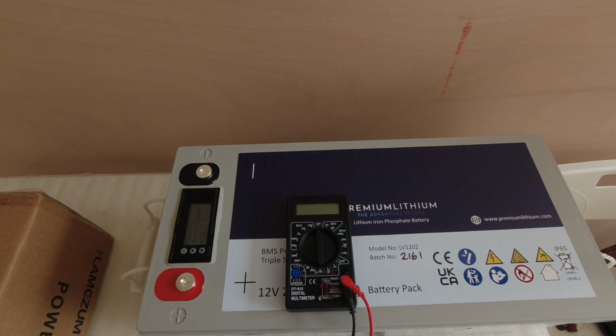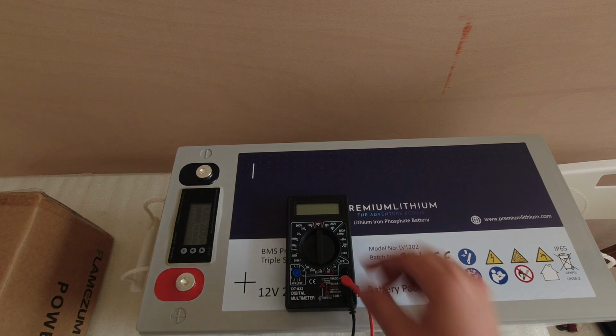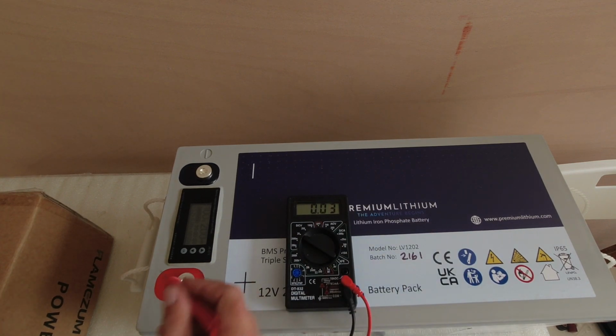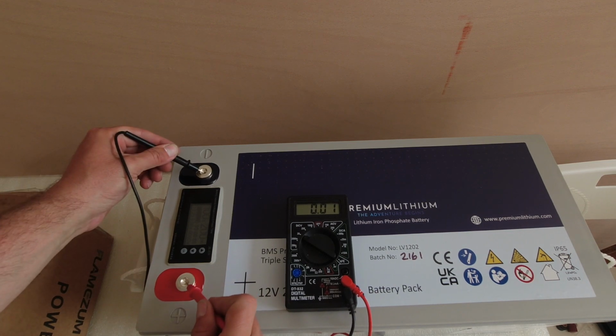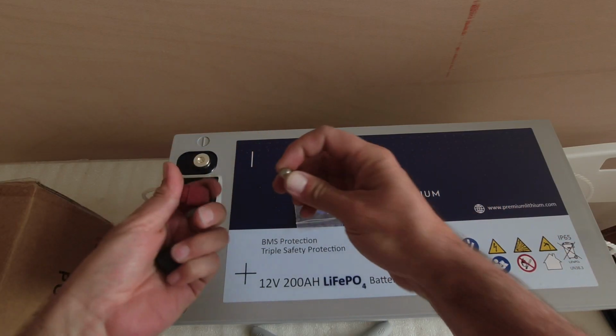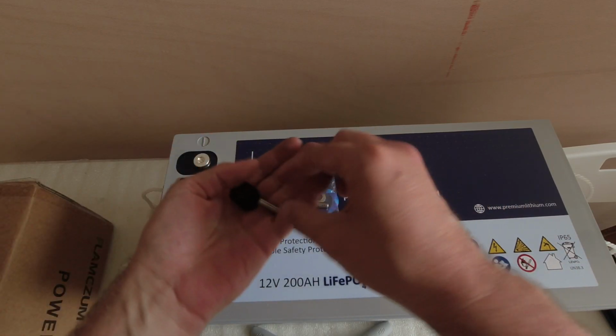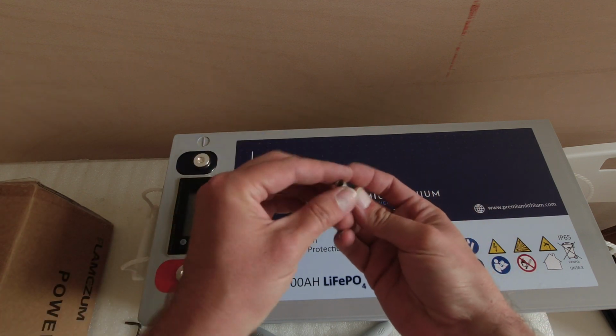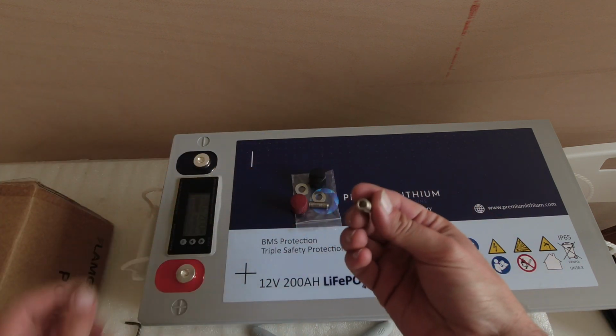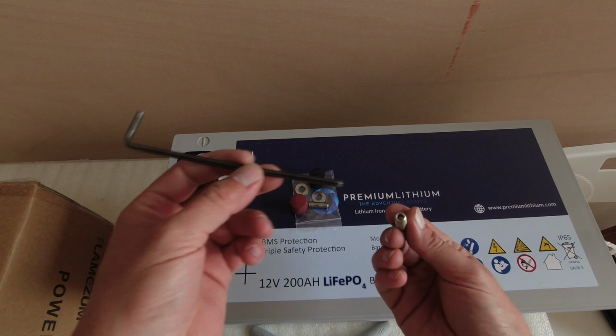I will now use a digital multimeter to check the voltage of the battery. I'll set the multimeter on 20 volts, connect the negative and the positive, and we read 13.4 volts. The bolts for connections are 8 millimeters in diameter, and you will need a 4 millimeter Allen key to fix them in place.